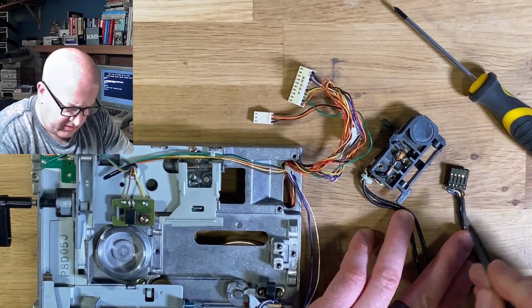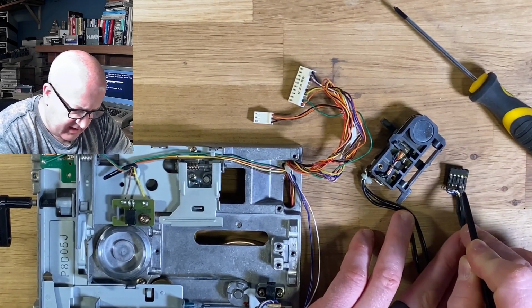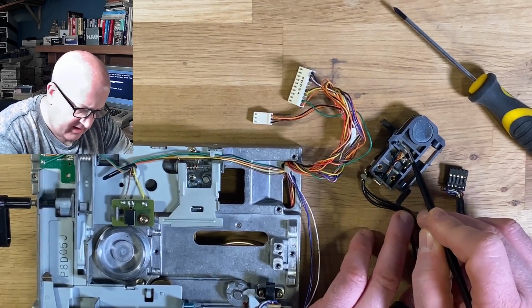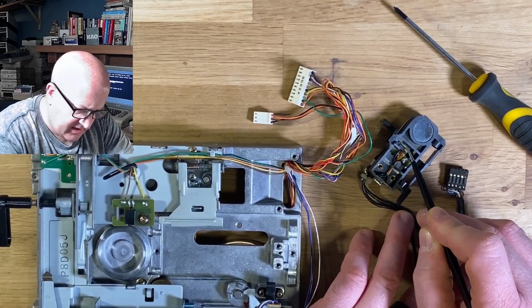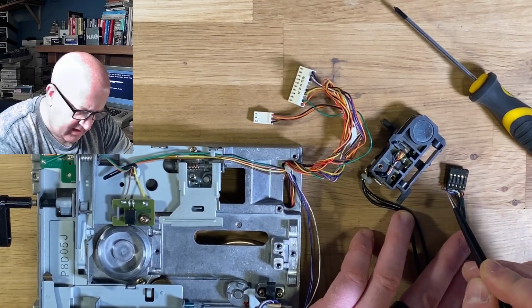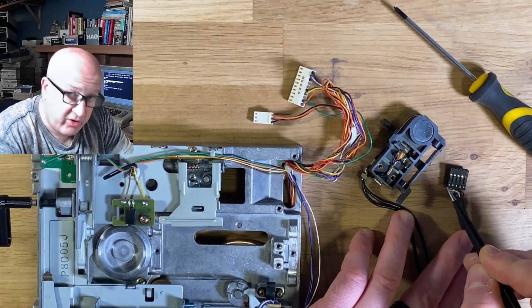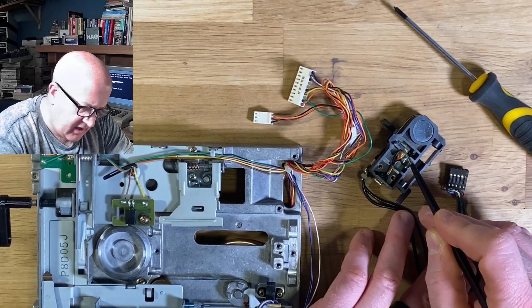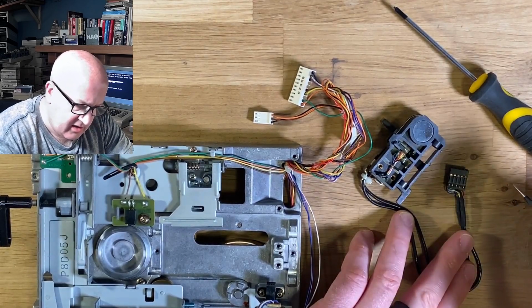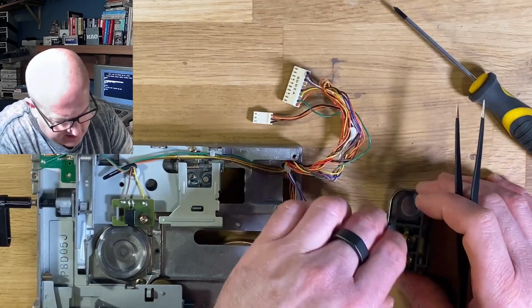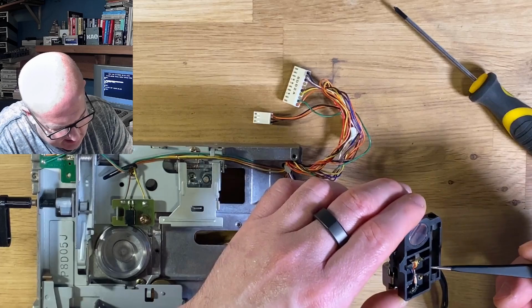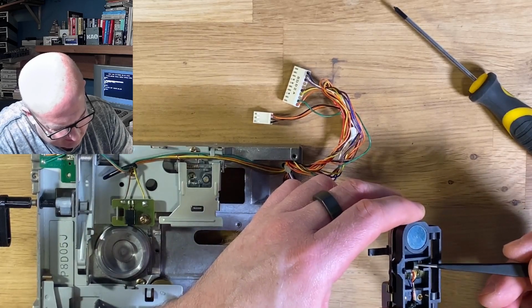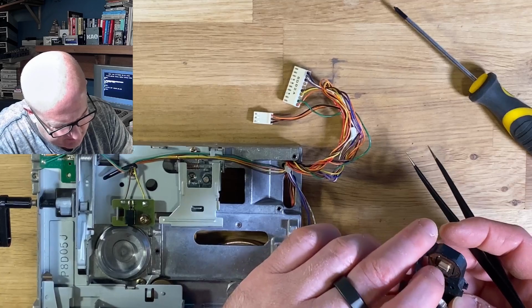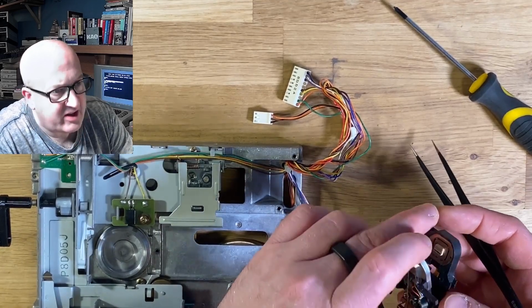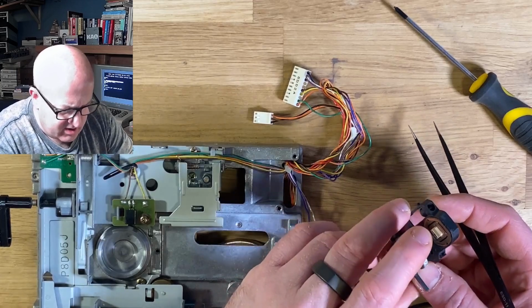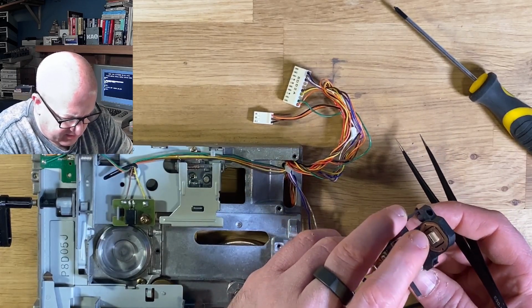I've just toned out between each of these connectors on the lower read-write head and the traces on this flexible connector here, and there's continuity, so there's no break between here and here, which is a bit sad because that suggests that the break must actually be either where this flexible connector goes into the head or within the head itself, and I think it's beyond my wit to repair that.